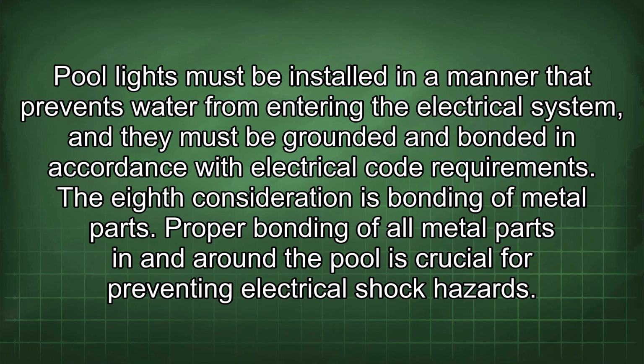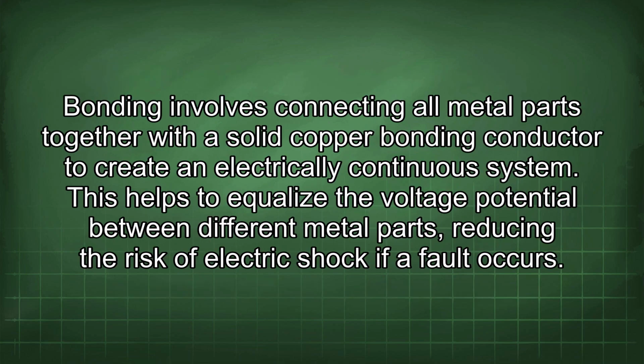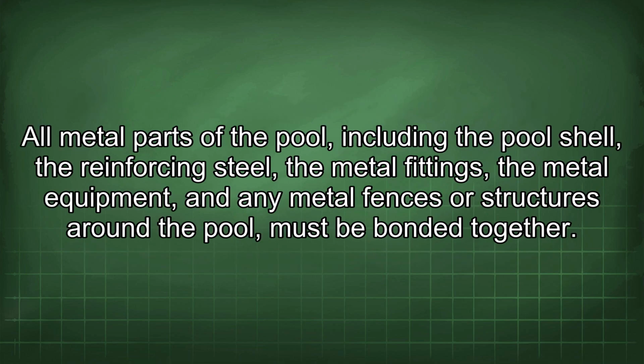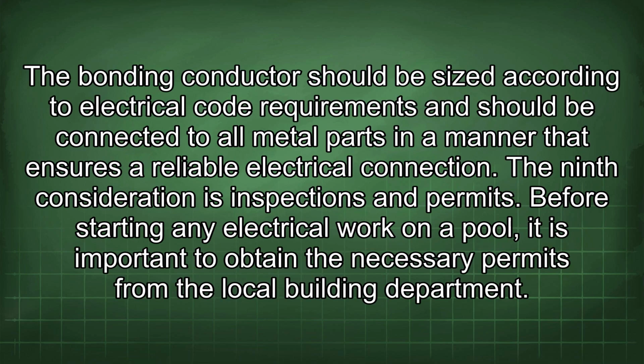The eighth consideration is bonding of metal parts. Proper bonding of all metal parts in and around the pool is crucial for preventing electrical shock hazards. Bonding involves connecting all metal parts together with a solid copper bonding conductor to create an electrically continuous system. This helps to equalize the voltage potential between different metal parts, reducing the risk of electric shock if a fault occurs. All metal parts of the pool, including the pool shell, the reinforcing steel, the metal fittings, the metal equipment, and any metal fences or structures around the pool, must be bonded together. The bonding conductor should be sized according to electrical code requirements and should be connected to all metal parts in a manner that ensures a reliable electrical connection.